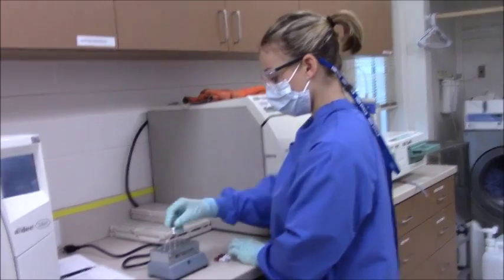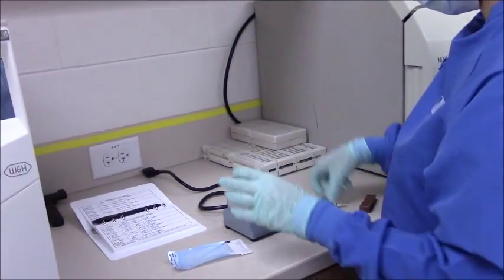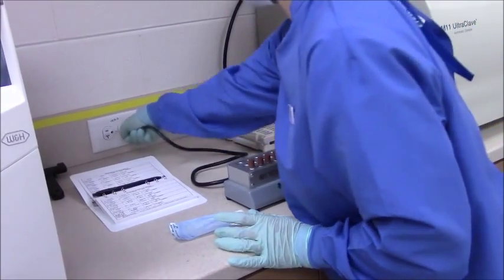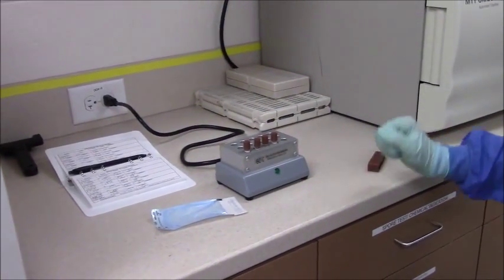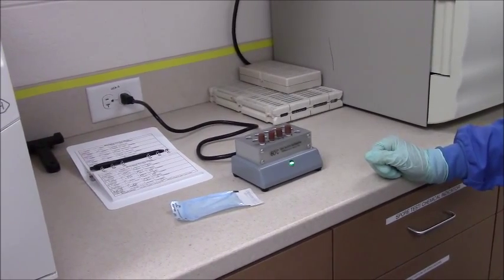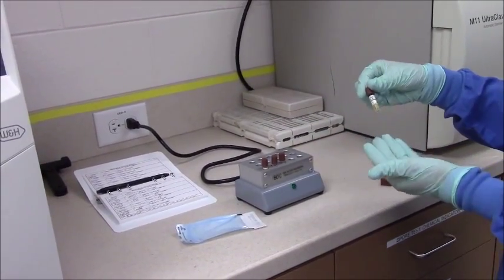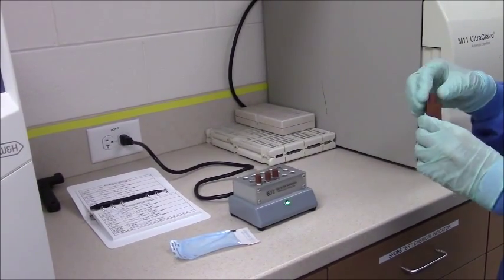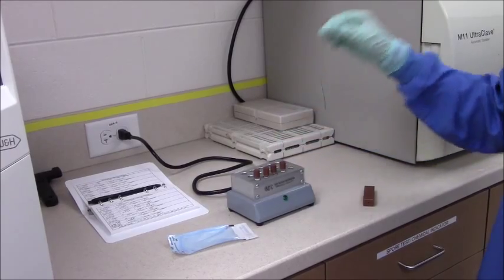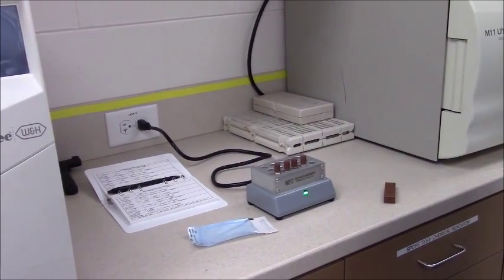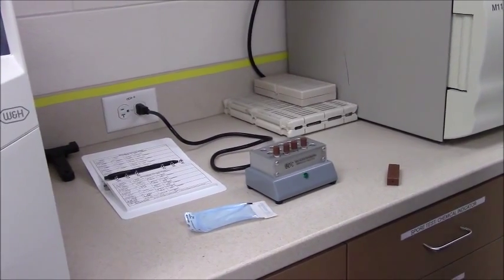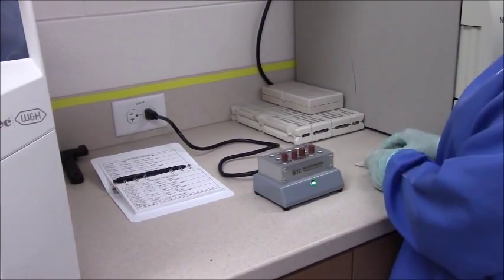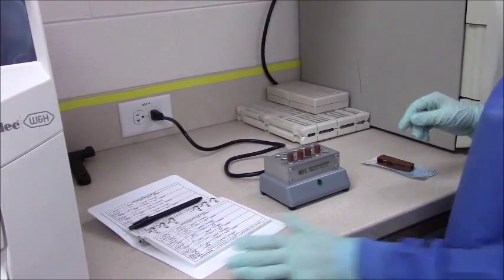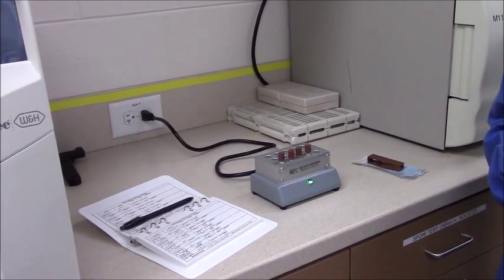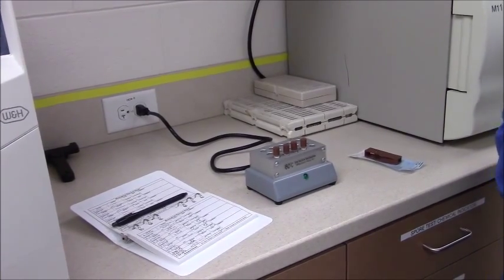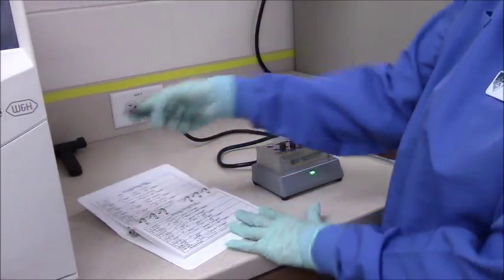Put each capsule in the incubator. Be sure the incubator is plugged in and does not come unplugged for 24 hours. There should be a control, and it should be labeled, and it's to be crushed before putting in the incubator. Do this at the time you add the first capsule, after it has come out of the sterilizer. The spore test should be read at 24 hours. To read the spore test, the control should turn yellow. This means that it's positive. The capsule that has been run through the sterilizer should not turn yellow. They should be purple or brownish in color, indicating a negative test result. Make sure the information is recorded on the log sheet.